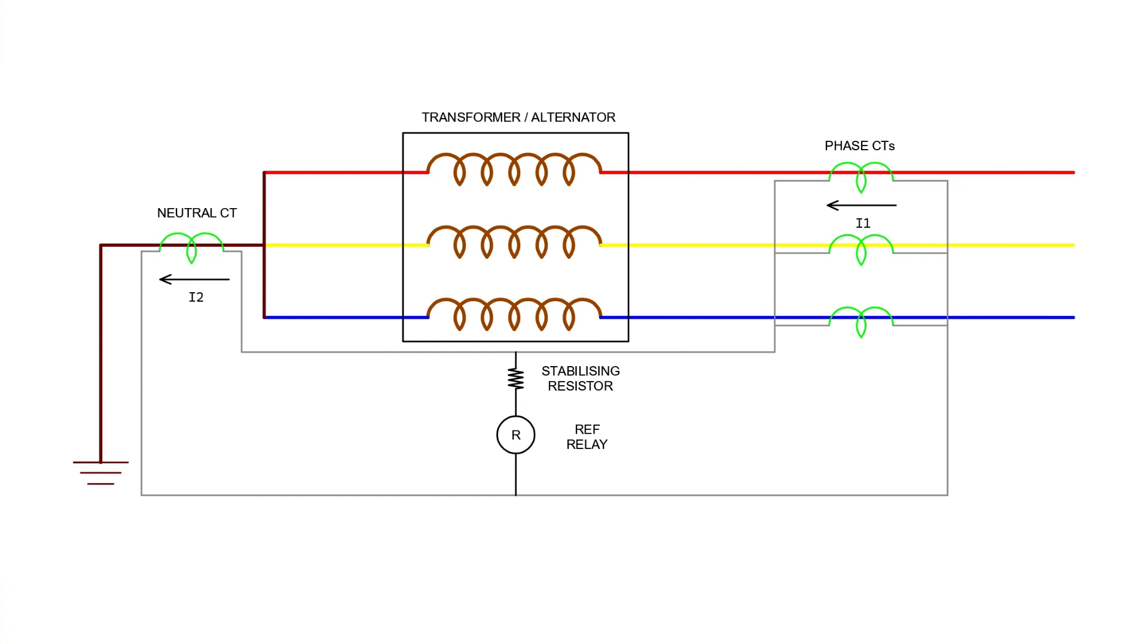This resistor is calculated such that under an external fault condition, that is for full fault level, the voltage developed by the unsaturated CT shall not circulate more current than the setting in the relay, thus preventing the relay from operating for an external fault and chattering.